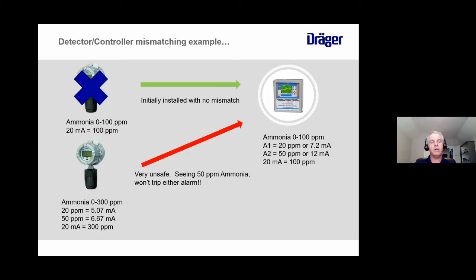I know I've been selling instrumentation for the last 10 years, and I don't know how many times I got that phone call from that customer. Hey, man, I just bought that new transmitter from you, and the damn thing, I'm putting 50 ppm ammonia on there. The controller's only saying I'm seeing 25. Well, that's what happened, they didn't change the range on the transmitter when they got it in. They just left it as the factory defaults. That's a very unsafe situation.